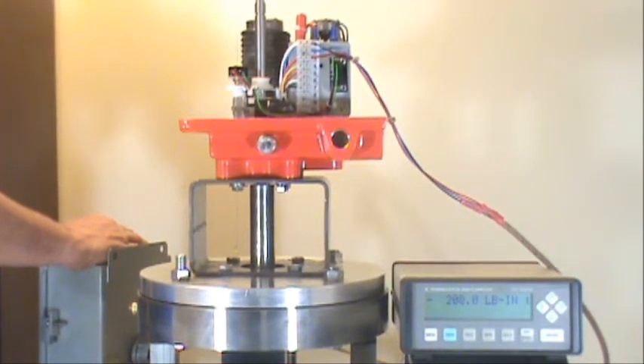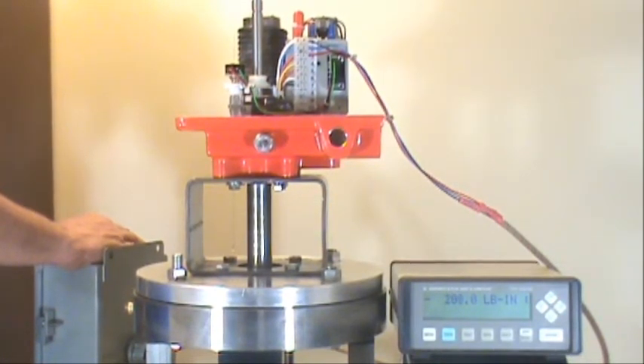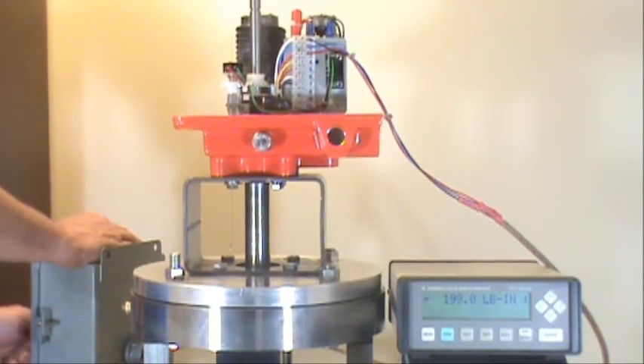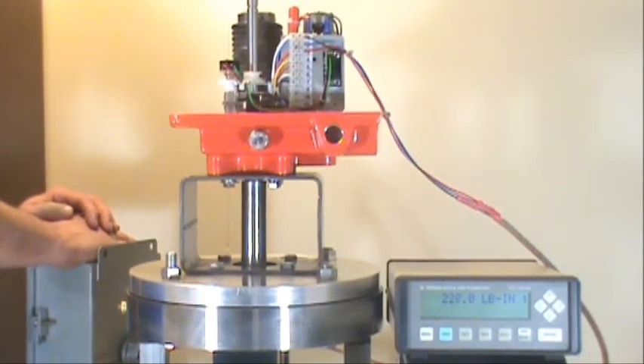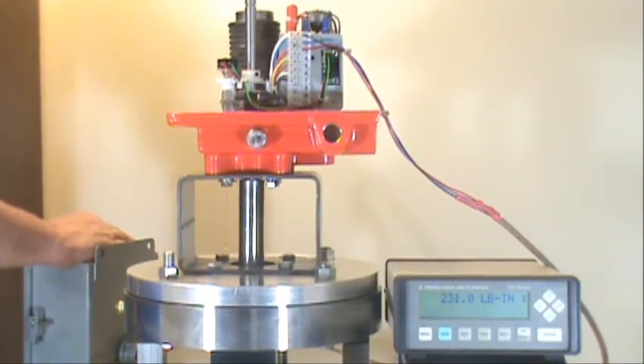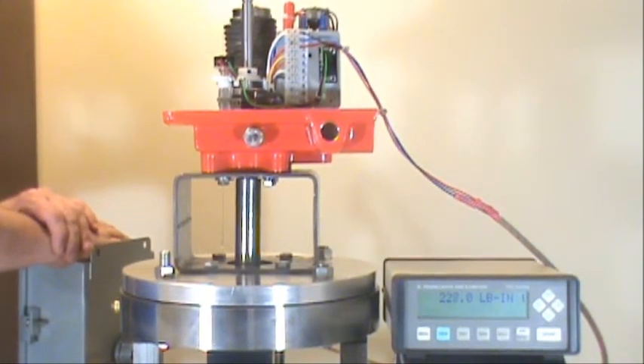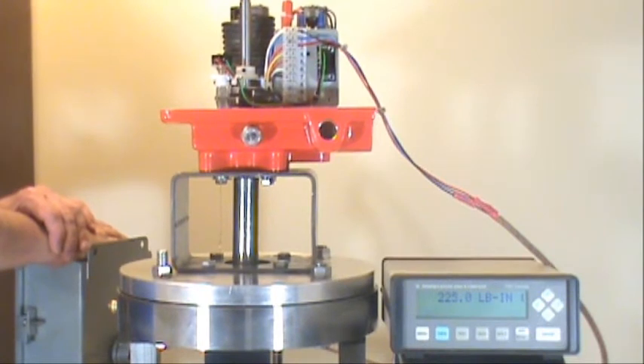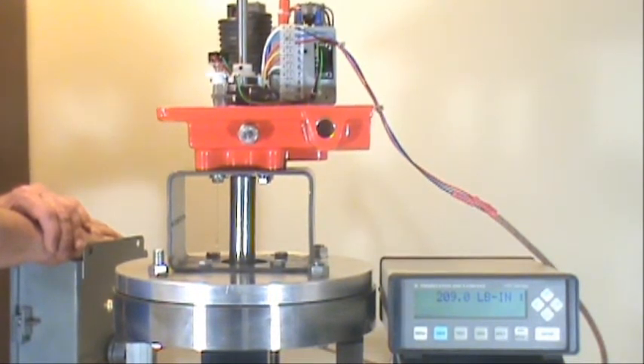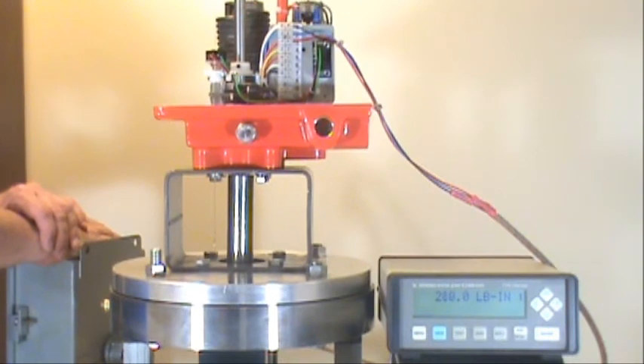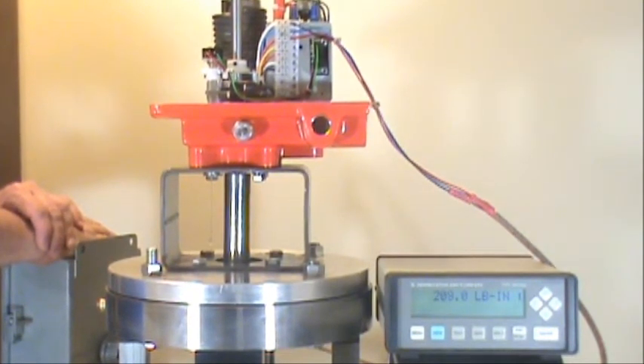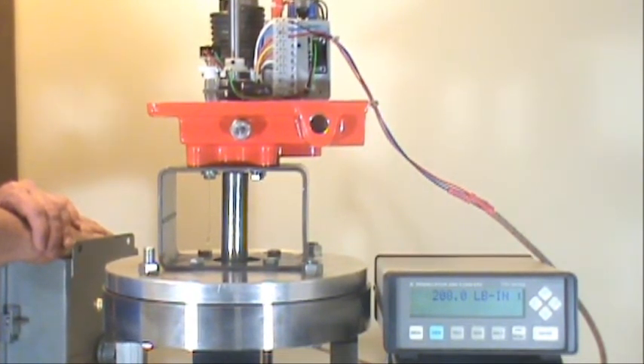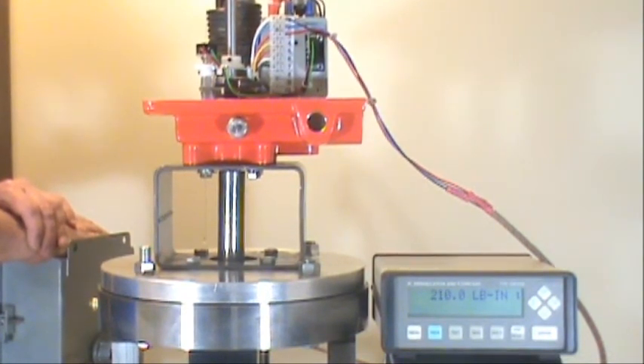Okay, now we're in the full open position. We're going to run it closed. So the actuator is all the way closed. And as you can see, we were up over 230 inch-pounds at one point in time. So the actuator is getting the torque that it's rated at.